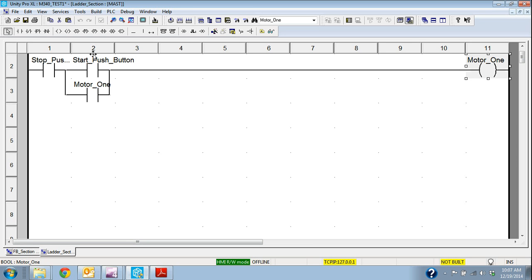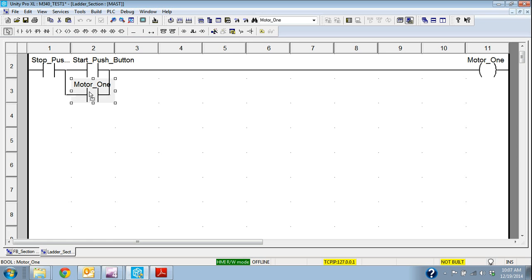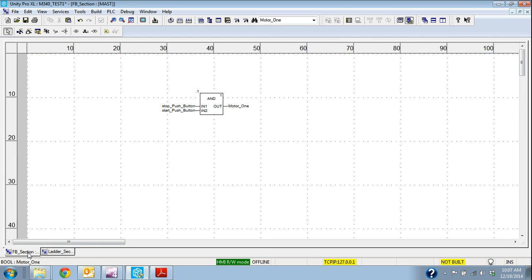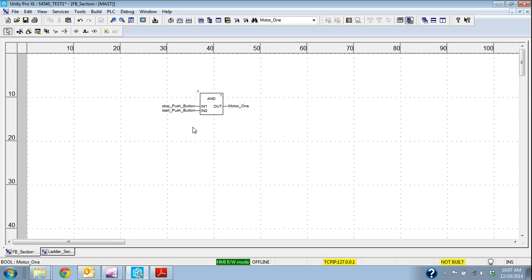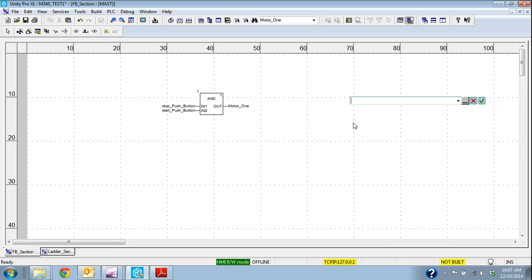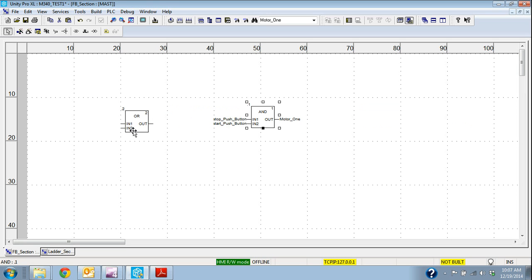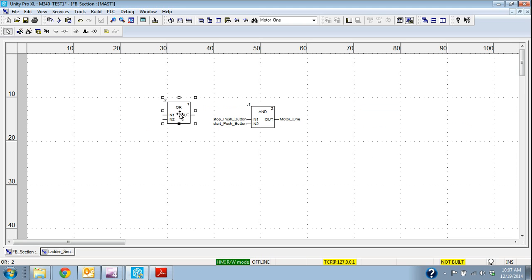Well if I come back I have this parallel circuit here or this hold in and ladder and that's an OR function because I can have the start push button or motor 1. So if I want to add that it's on the start push button I go right click again data selection. This is an OR block, OR, and you can see this is an elementary function block that has that I can make that adjustment as well.